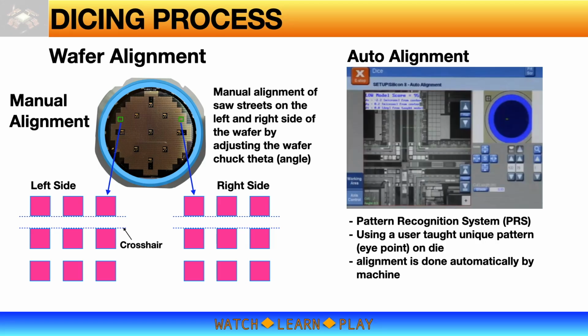In an auto alignment method, the user will select and teach a unique pattern that the machine will use as a template for wafer alignment. The PRS system is able to detect position and rotation of the taught pattern and translate that to the position and rotation of the wafer. With the PRS information, the wafer rotation, which is the wafer theta alignment, is adjusted automatically until the wafer is aligned or straight.